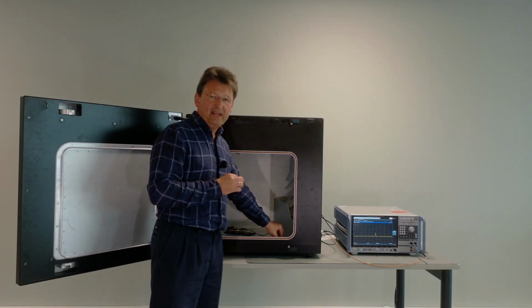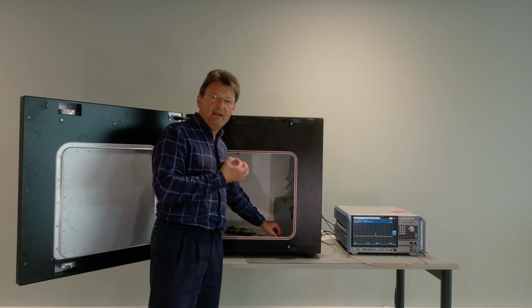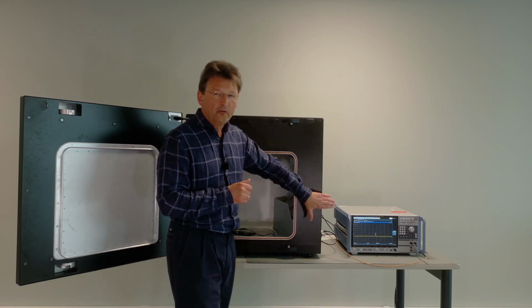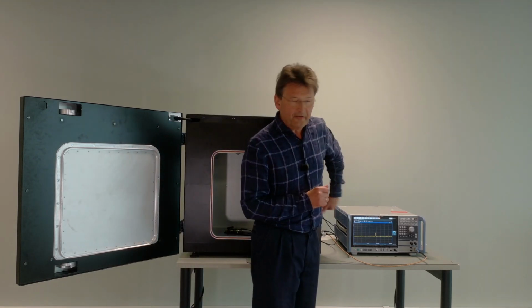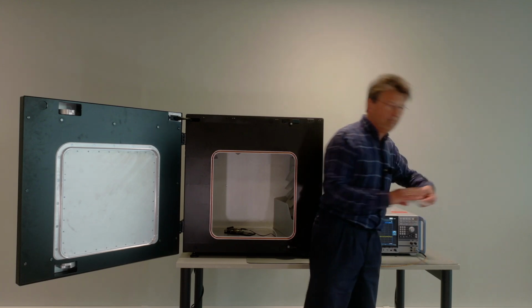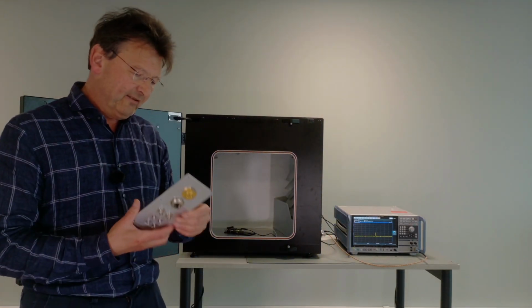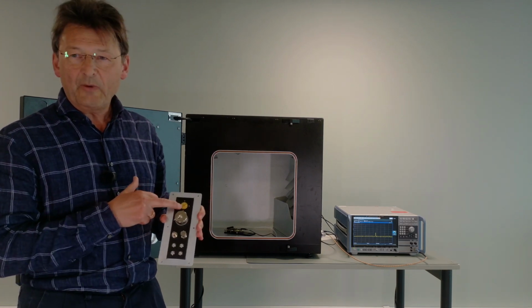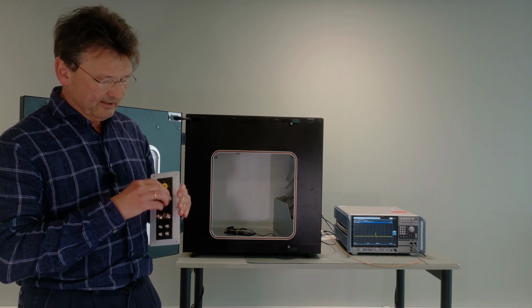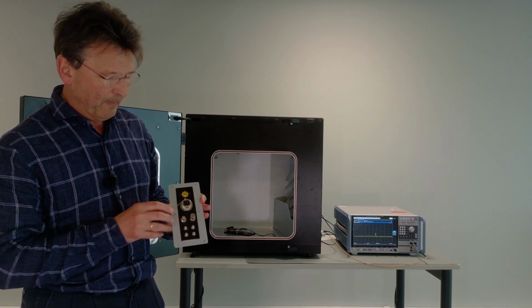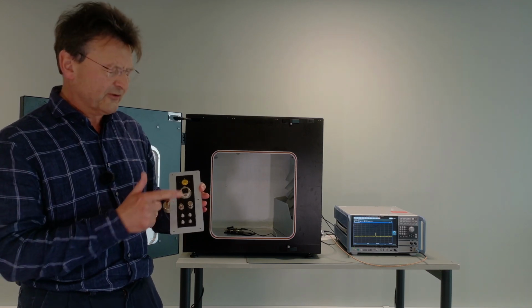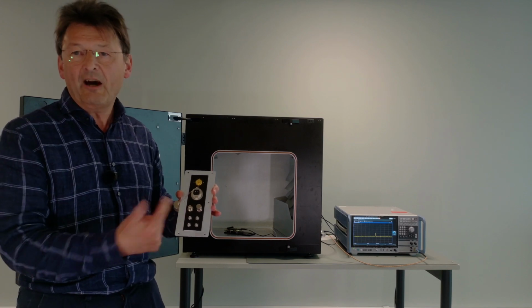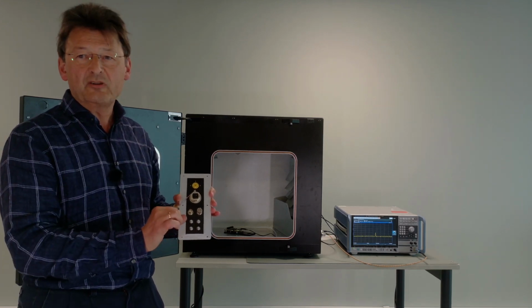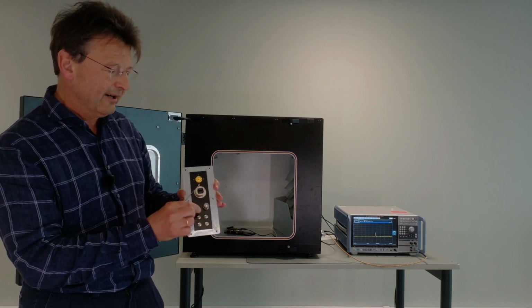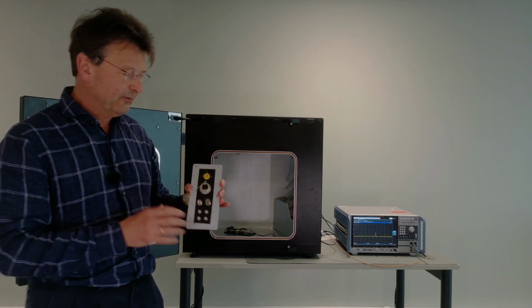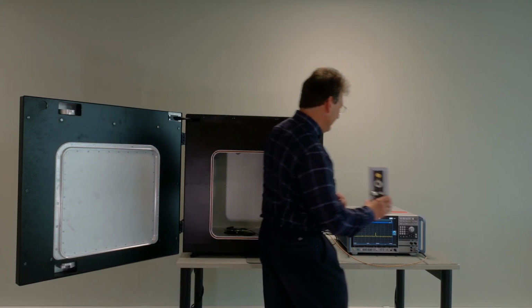Now, how are we bringing in the DC and how are we bringing in the USB control or any other type of control? Well, on the side of the chamber, there are panels. And I do have an example here of a panel. And you can see here the outside. For example, here you have some waveguide. If I open this, you have a USB connection of this panel. There are coax connections, BNC connections and coax connections. So you can feed in RF into the chamber, or you can basically measure the fields inside the chamber by bringing the RF outside. So there is a lot of flexibility in the configuration of this panel. So we have one of these on the side of the chamber.